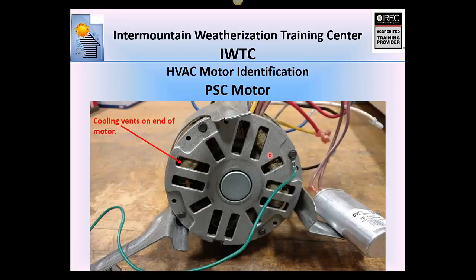A question arises about Herm terminals on capacitors — those are for compressors, not blower motors. On condensers there's a multi-capacitor with common, Herm, and fan terminals. For this presentation the focus is strictly on furnace blower motors. PSC motors on evaporative coolers are still standard PSC motors; someone may have replaced a capacitor with whatever they had available.